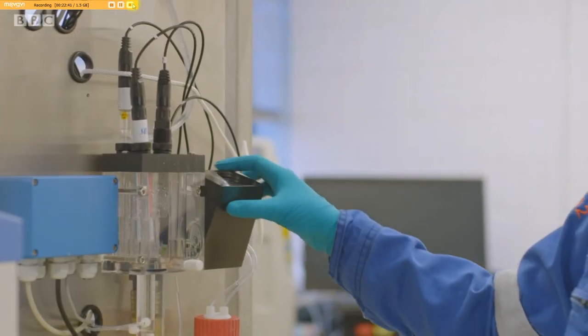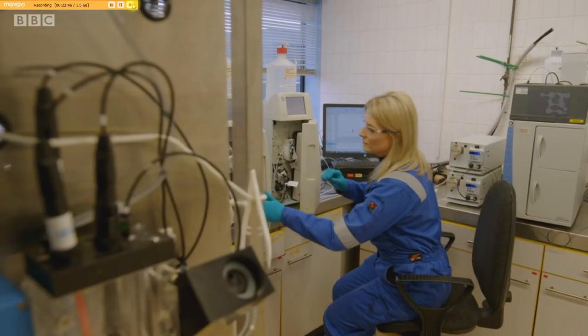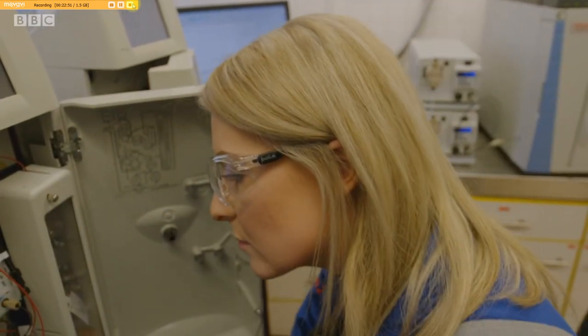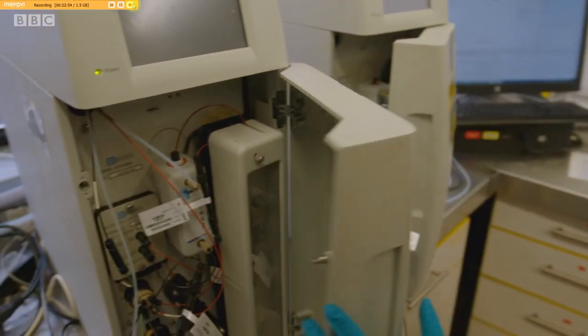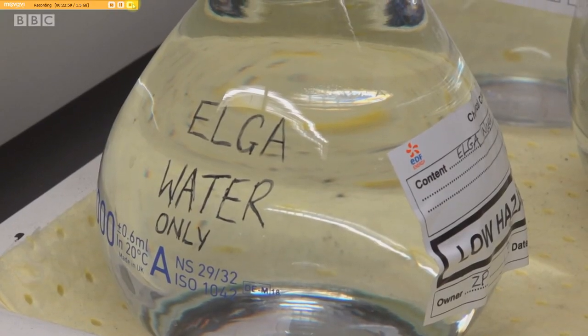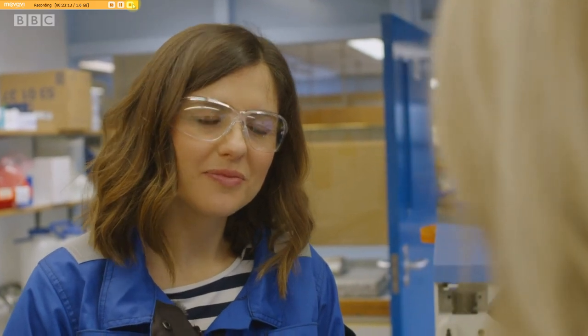The outage is underway, but normal life continues at Heysham 2. Chemist Beth Thomas is monitoring the water used in the boilers in the reactor hall. It comes from the regular water supply but is further purified at Heysham. We're testing for really, really low levels of anions and compounds — looking for parts per trillion. We're controlling our feed water to really tight specification to make sure our water is super pure when it goes into the boilers.